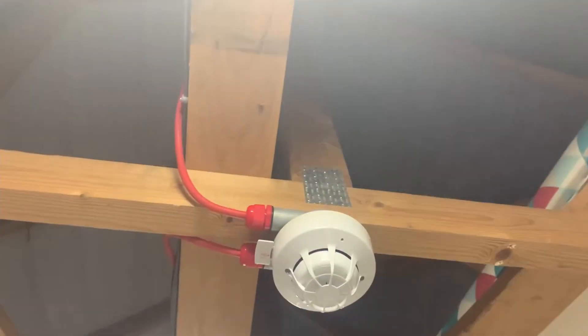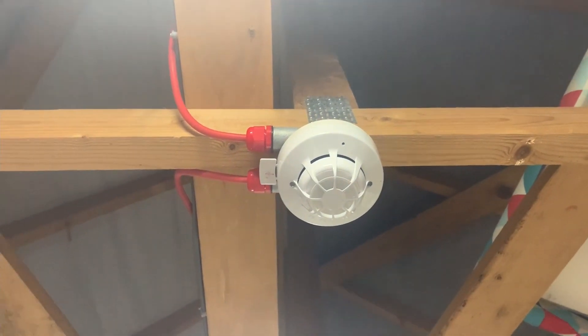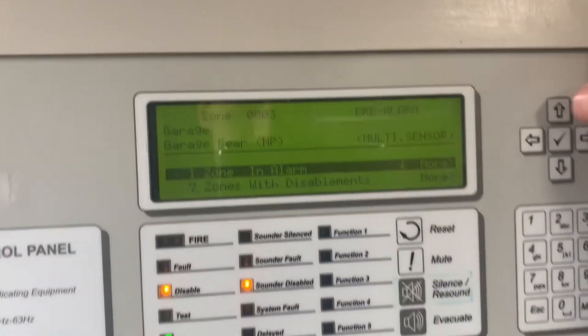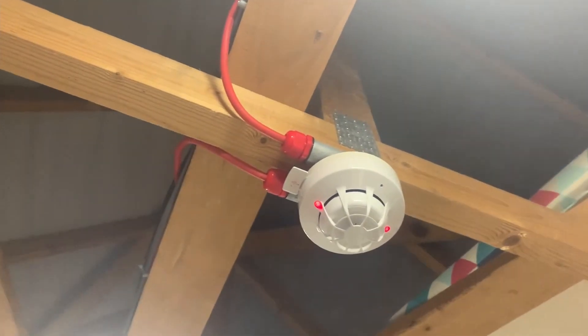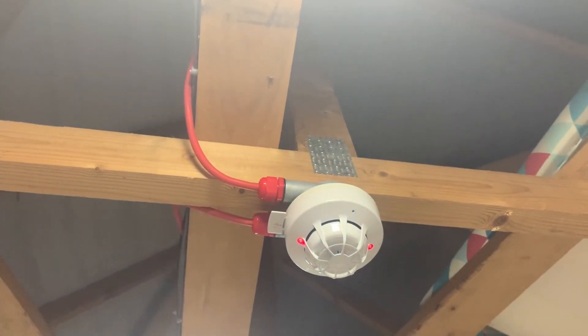I really hope this is not one of those multi-sensors that just don't work. This is a Discovery one, but all the polling is currently switched off. There we go — and that's the pre-delay. Oh no, it's in pre-alarm — my bad. Garage rear multi-point. Will that go into full alarm? I'll have to check this multi-sensor because I had issues with dirt in it, although it was not dirty at all on the inside. I've always had issues with multi-sensors — the panel says all my multi-sensors are dirty, but this one seems to be working okay-ish.